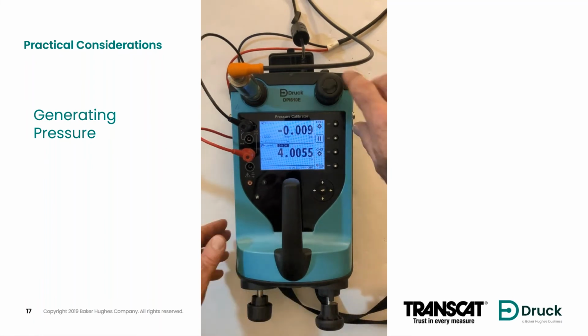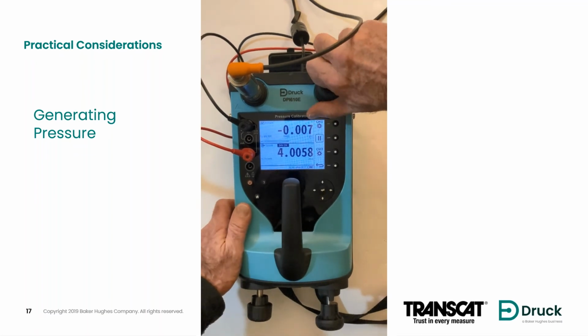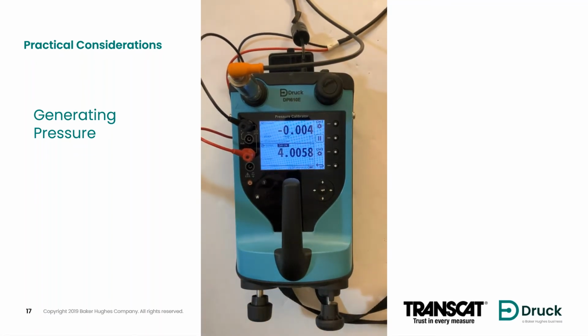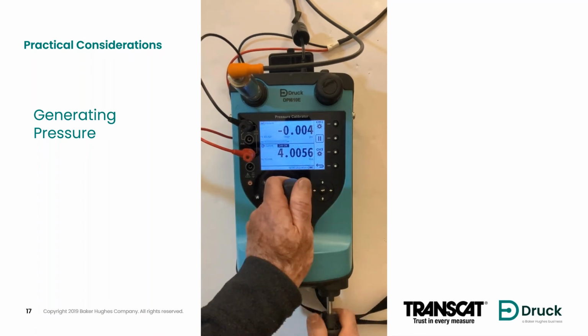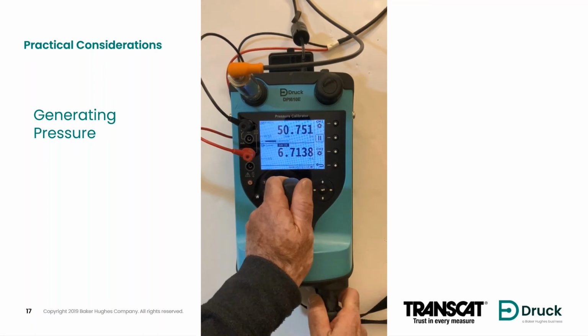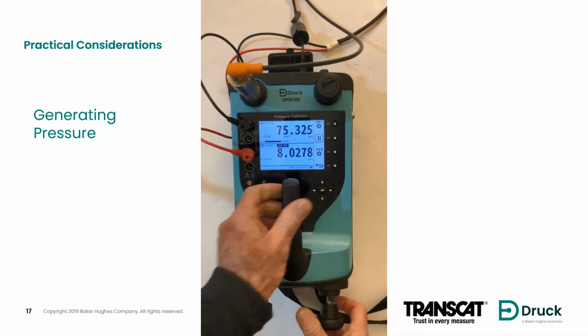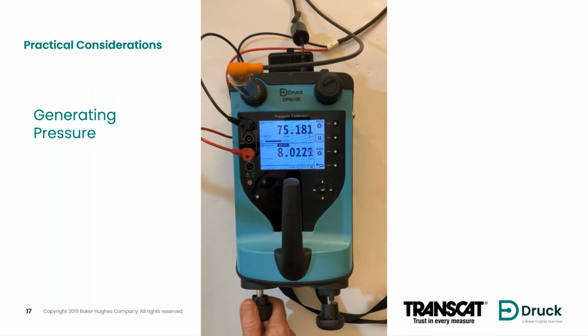So the first thing I'll need to do in generating pressure is to close the vent valve. And then I'm going to use the convenient, robust handle to generate pressure. I'd like to point out that that's one pump stroke. I'm getting about 25 PSI per stroke with this setup, with this transducer. So I'm going to go up to 75. It's a 300 PSI sensor. I just went up to 25% of its full scale range, 75 PSI. So we would expect to see 8 milliamps coming out. I did a little bit of adjustment there, and it seems to have settled out fairly well.